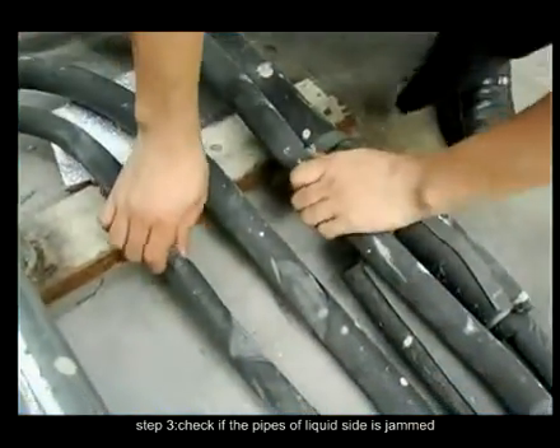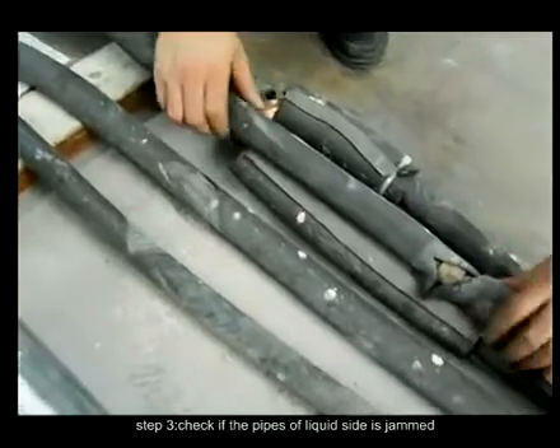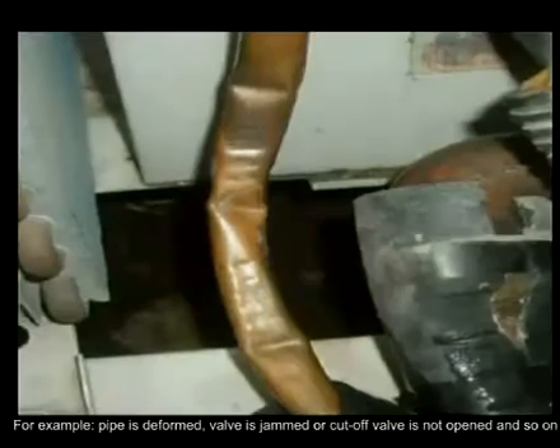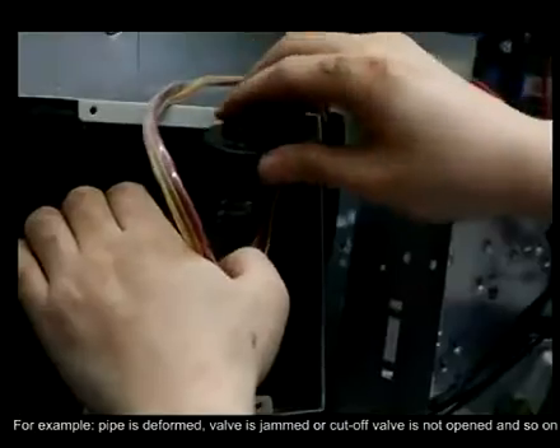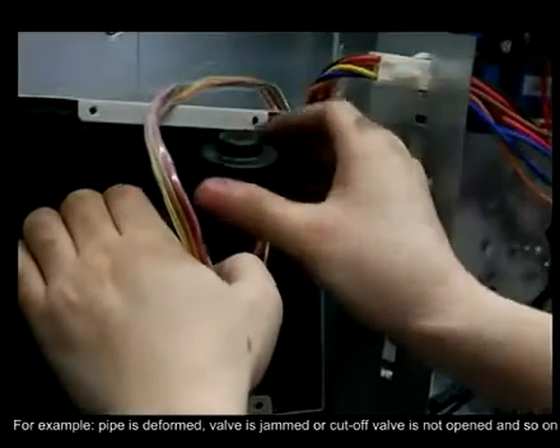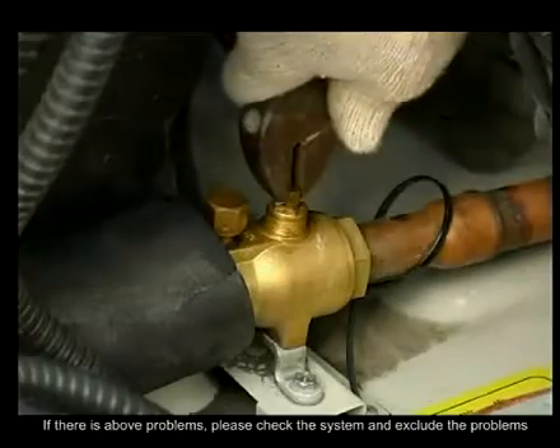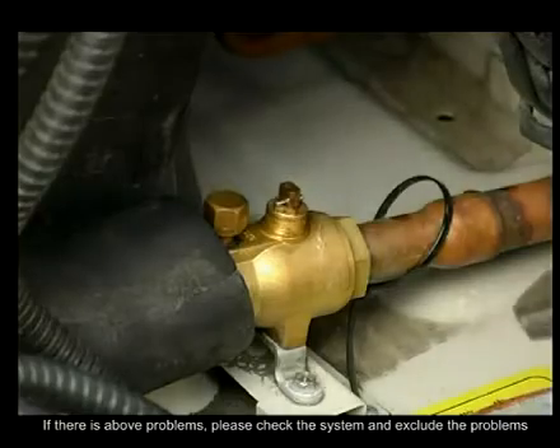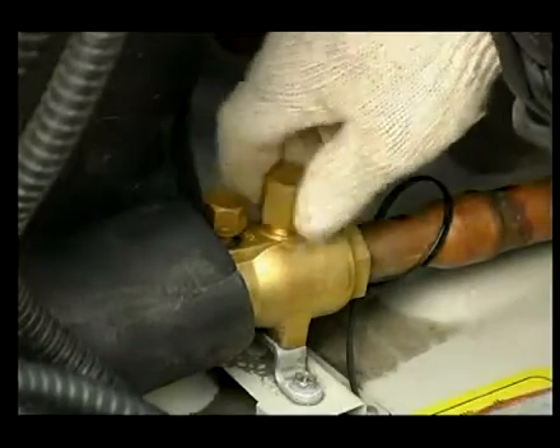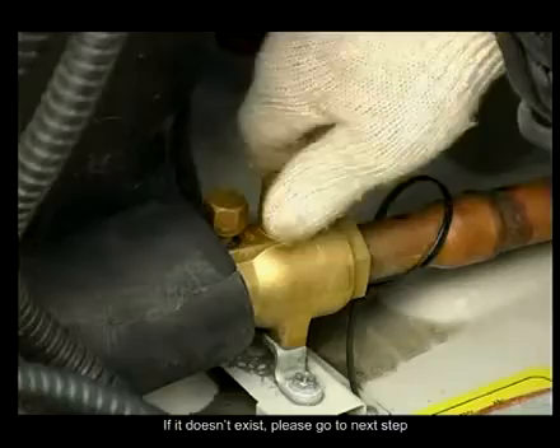Step 3. Check if the pipes of the liquid side are jammed. For example, the pipe is deformed, a valve is jammed, or a cutoff valve is not opened, and so on. If there are the above problems, please check the system and exclude the problems. If they don't exist, please go to the next step.